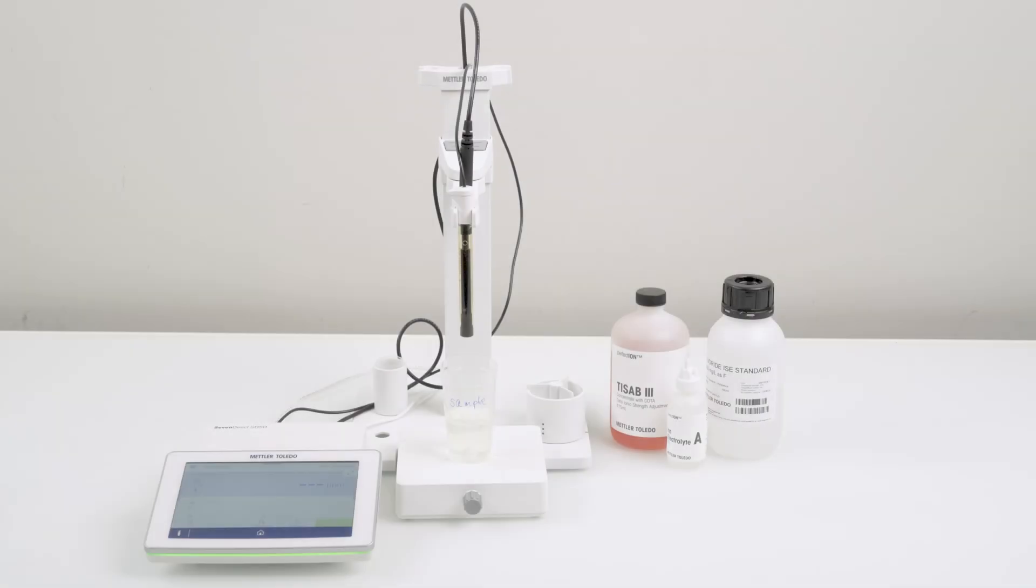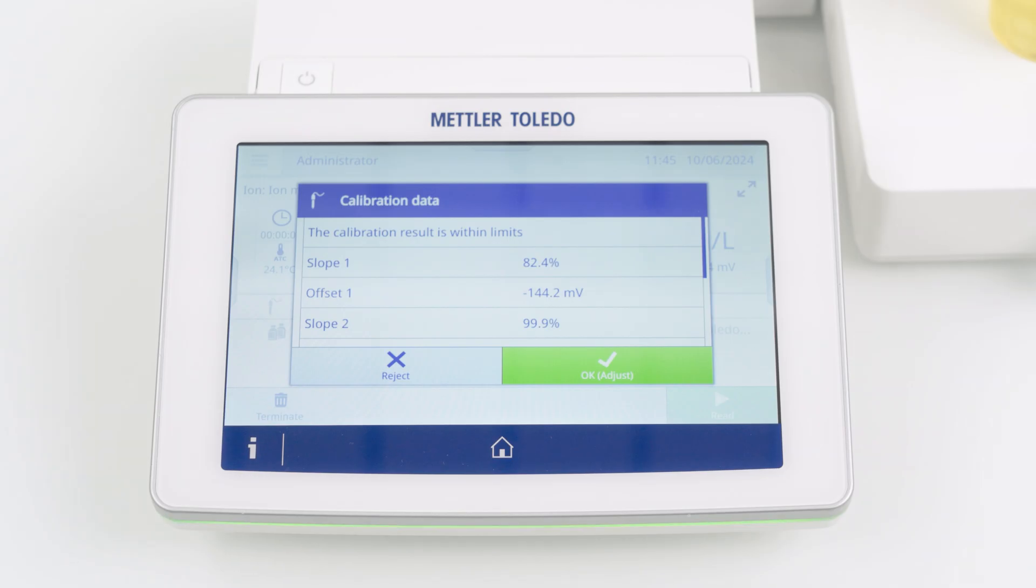If you have attempted calibration and it was not successful, the membrane is likely the cause. As the first step, try and regenerate it.